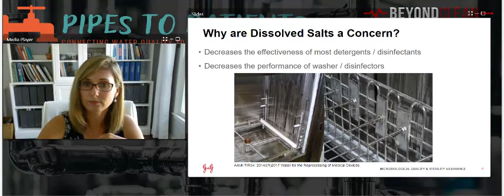So the other thing we have to talk about is ionic molecules. We talked about them a little bit before, but why are they a concern, and really, what are they? An ion is an electrically charged atom or molecule. Ions are really important in water for medical device reprocessing, and the ones we're most particularly concerned with are chloride, iron, copper, and manganese. Any of these excessive ionic molecules can really start to cause things like pitting.